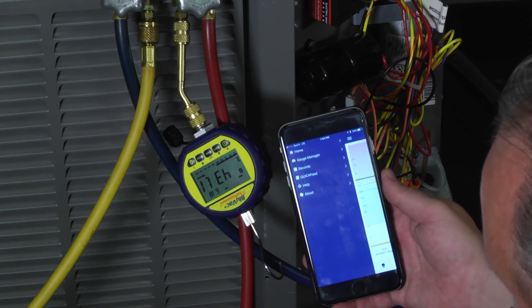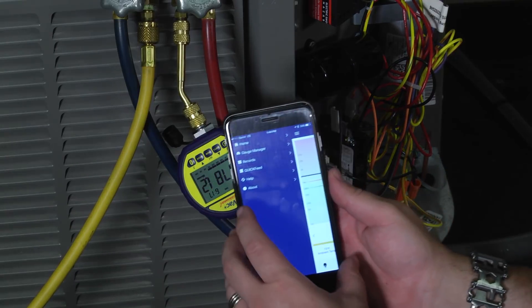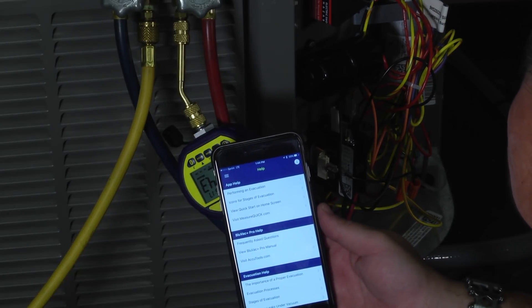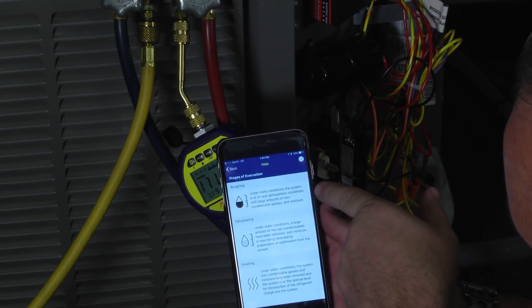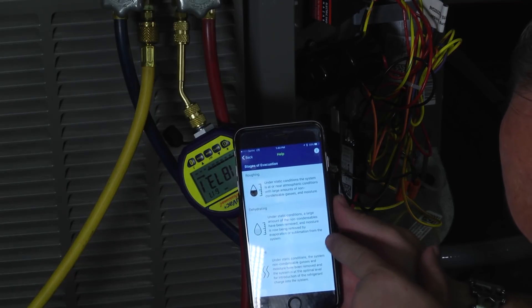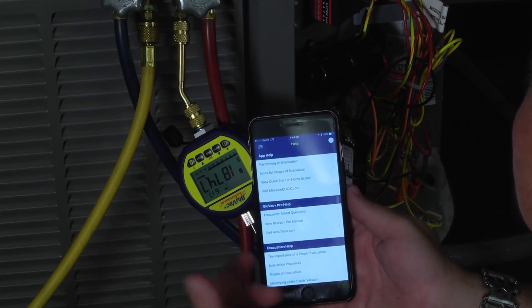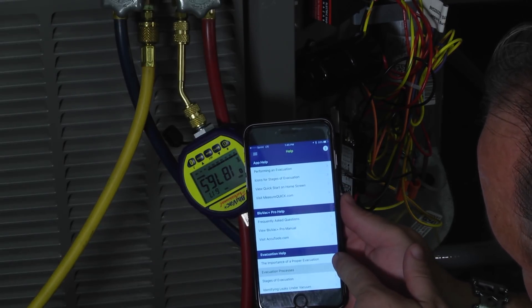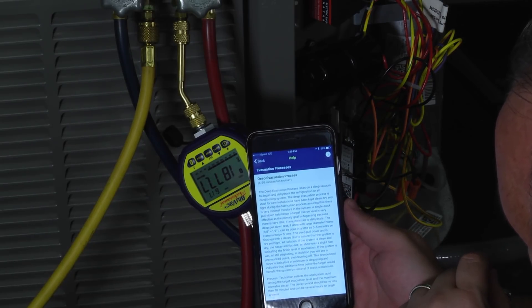I've worked with the folks over at MeasureQuick — Jim Bergman and his team — for a long time, and I know that they're dedicated to educating. One of my favorite features of the BluVac app is the help screen. Look at all the information it can give you: help on how to perform an evacuation, all the icons for stages of evacuation — roughing, where we've got a lot of moisture present; dehydrating, where a large portion of moisture has already been removed but we're still dehydrating; and finishing. There's also a whole bunch of helpful items on evacuation itself, so you can educate yourself and learn more about evacuation and dehydration.